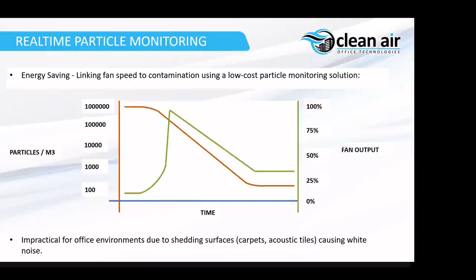So unfortunately, we couldn't really apply that technology to workplaces, but we did realise that there was potentially an opportunity to apply this to clean rooms. So one of the things we're investigating now is using this for real-time HEPA monitoring. So rather than going into a space every 3, 6, 12 months and doing particle counts, we could monitor the air coming off of the HEPA filter around the clock and link that to an alarm system. So should a filter become damaged, suddenly let by, or be a massive source of room contamination, that would trigger an alert, could trigger an investigation into the production line. And also, it could be very useful in containment facilities as well, couldn't it? Where the filters are a safety component.